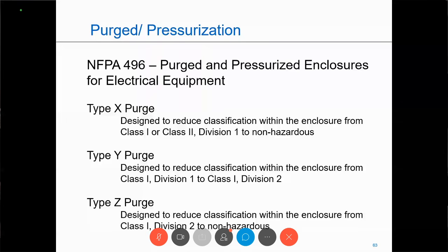My Y purge is when I have a Class 1 Division 1 area and I put in Class 1 Division 2 components. And my Z purge, the most common, is when I have a Class 1 Division 2 area and I have non-hazardous components inside. Now with Y purge and Z purge, the interlock is optional, but I do need to have some type of signaling to let me know the purge has been lost. And as you can see here, NFPA 496 gives you the information that you would need to further look at purge and pressurized equipment.